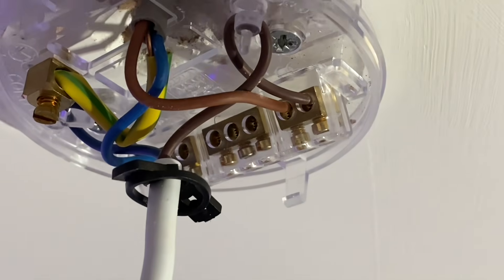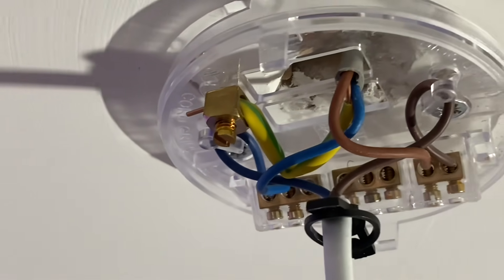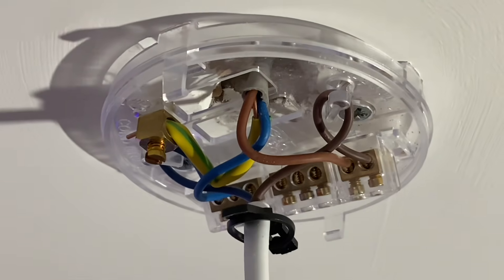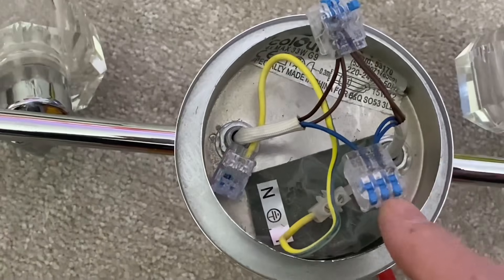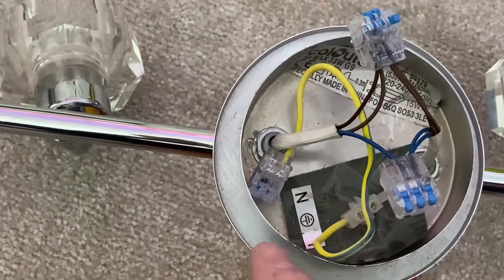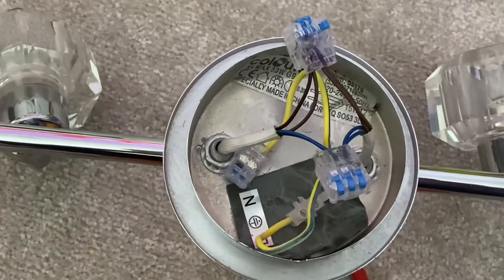I've unscrewed the ceiling rose and pendant in the lounge. Another little bit of interest - you can see we've got one switching line, a looping terminal not being used, one neutral, and one CPC. So again they've used the two plate method, taking the feed to the switch. Just jump down to see the back of the light fitting - I've made a few modifications and added some In-Sure connectors from Ideal Industries so I can just make these three connections.